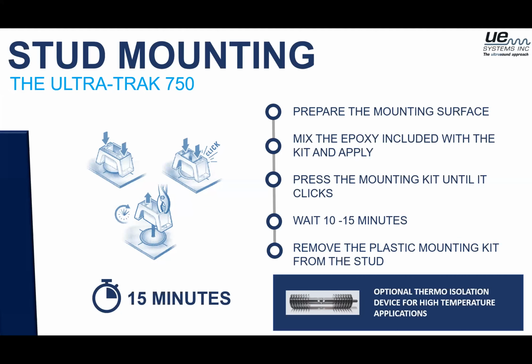And we do have a thermal isolation device. If you have a bearing that runs really, really hot because of some of your applications and we exceed our temperature limit of that sensor, we have these thermal isolation devices, which still provide a very great repeatable signal, but allow us to stand off, use the ambient air to cool it down so we don't burn the electronics. We have not yet found a bearing that we cannot monitor.